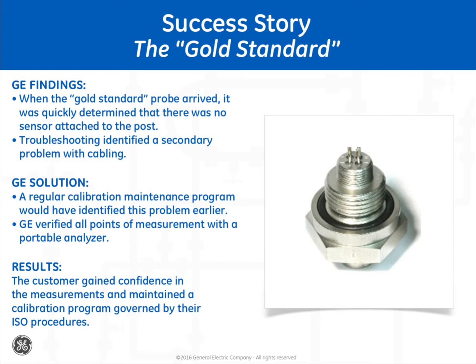In this case, two faults had occurred. The customer had installed the moisture probe without a sensor. This was intended to be used as a temporary plug for their sample cell and sample system. And the cable to the analyzer was not properly shielded, causing it to read a rather steady offset that only varied with environmental factors. A regular calibration maintenance program would have revealed this problem much earlier.